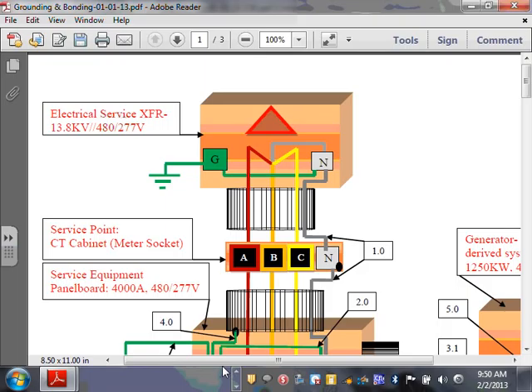Does that make sense? So this box here, what's going to ground this box? A neutral. Is it wrong if I drove a ground rod right here and grounded the neutral? No, there's nothing wrong with that either. But the code allows you, right in this box, to bond your neutral to the termination box. Why can we do this? Because we're on the line side of the disconnect. Where's the main disconnect? The service disconnect exists in this 4,000 amp switchgear here.